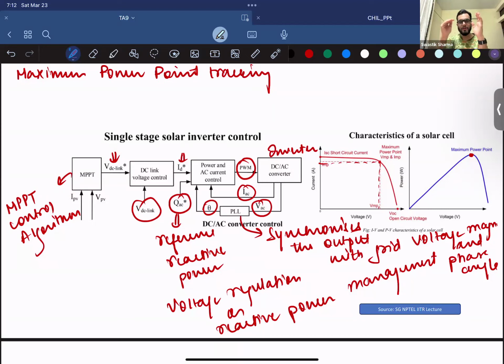This is only possible if you measure it properly, since you are already using the output of your converter, your VAC and IAC, to lock it to the phase of your grid frequency. So the voltage is locking itself to the grid voltage magnitude and phase angle. But how your ID current behaves, this ID star, will only flow if it's flowing from a higher reference to a lower reference. So this ID star reference gives the PWM voltage frequency to be able to match that voltage level. That's how the whole converter operation forms itself.